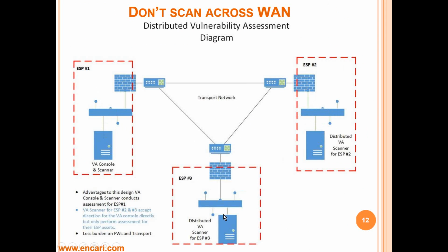So just to close up on this slide, any of these remotes, any of these scanners, if there are 50 boxes inside ESP number 3, that scanner is going to be asking each one of those boxes 150,000 questions. So let's keep it local and not make all that go across our firewalls and our poor little T1s and everything else, so that they don't lose connectivity and want to crash or deny legitimate traffic.